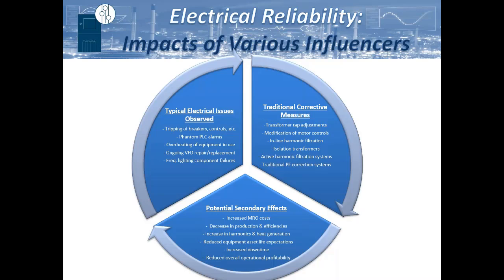Oftentimes it's easy to correlate heat with life expectancy. If we can reduce the operating temperature by 10 degrees, it extends the life of that component by 50%, right? That holds true with electronics as well. So if we can maintain a steady voltage level and minimize those harmonics, it allows the equipment to run in a much more beneficial environment, so that it can extend the life of those.